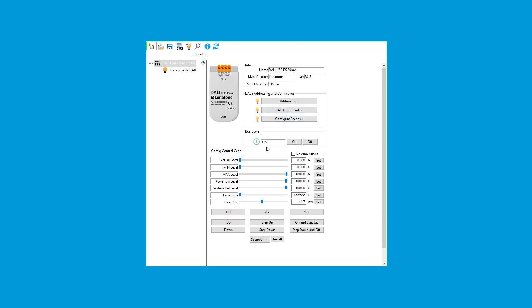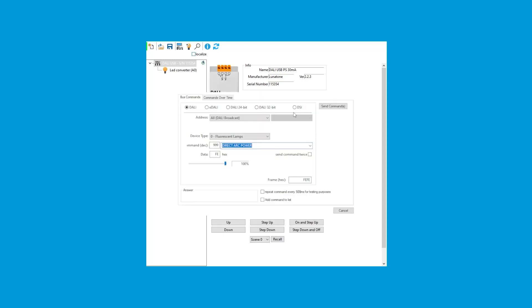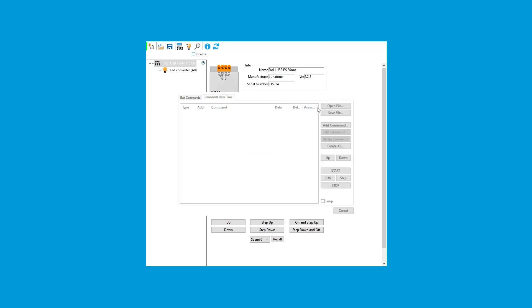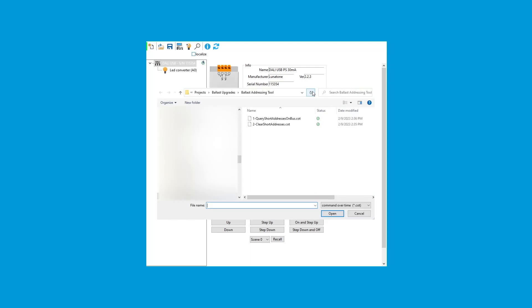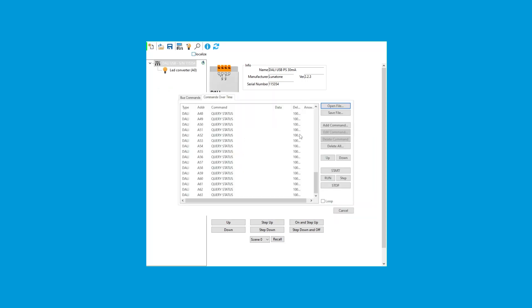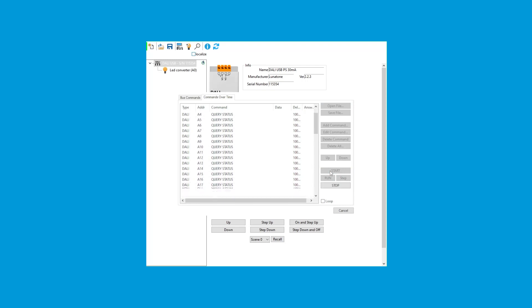Once you see that bus power is turned on, press the DALI Commands button. This will bring up a window allowing you to send commands to clear the ecosystem address. When the window shows up, click the Commands over Time button, and then click Open File. You're going to select the Query Short Addresses on Bus file that you downloaded from Lutron.com. Click the Start button and it will run through the list of commands.